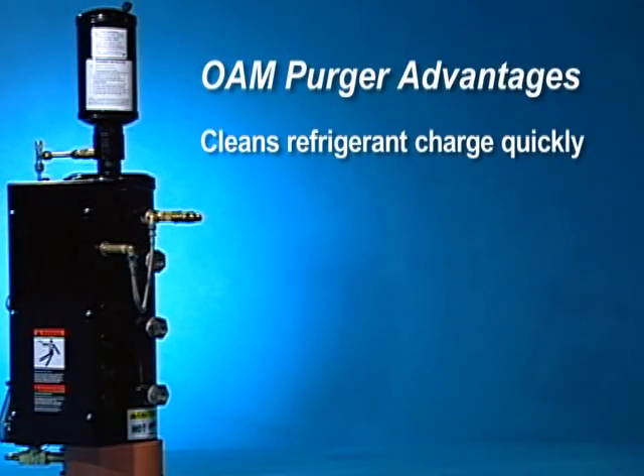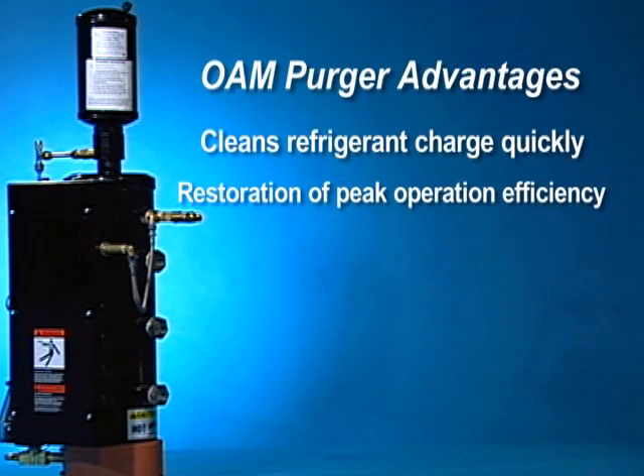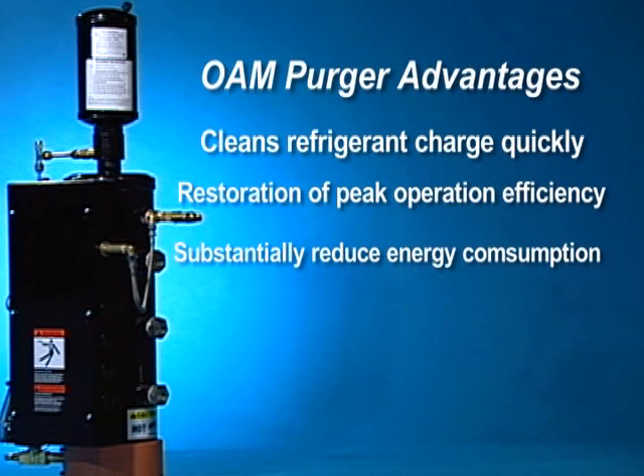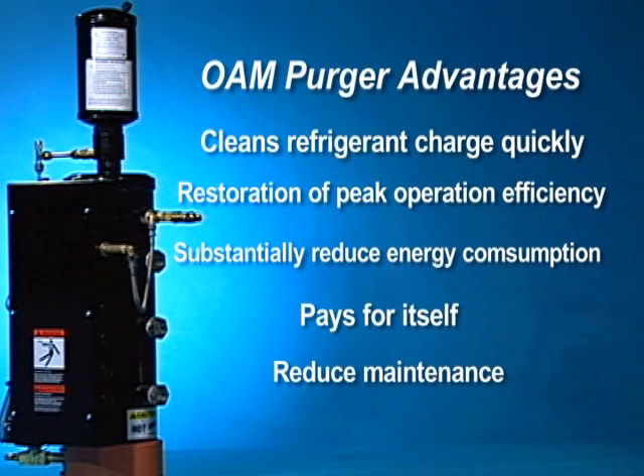Advantages to the chiller owner? The OAM Purger quickly cleans the chiller's refrigerant charge to only a trace level of oil. It quickly restores a chiller to peak operating efficiency. It substantially reduces energy consumption, saving the owner thousands of dollars in operating cost. The OAM Purger pays for itself. So, in effect, retrofitting an OAM Purger does not really cost the owner anything. In fact, retrofitting with an OAM Purger is a financial investment that keeps on paying dividends, in most cases thousands of dollars per year. Finally, it reduces maintenance and helps prevent premature failure.